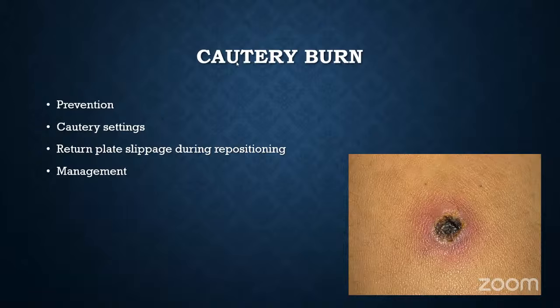We slightly increased the power setting every now and then. We didn't realize that when you raise the power, the cutting energy also will rise, and you need to see a proportionate increase in the cutting in the laparoscopy. If you feel that there's a discrepancy, it means that in spite of increasing the current, you're not able to cut the wall properly. It means that it's earthing somewhere else and you need to look out for these burns. If it does happen, how do we manage, Meenakshi ma'am?